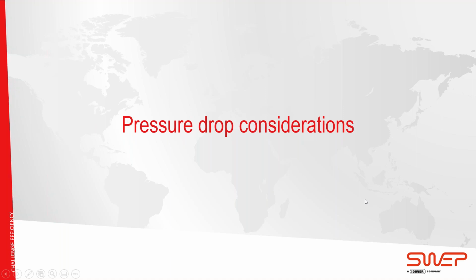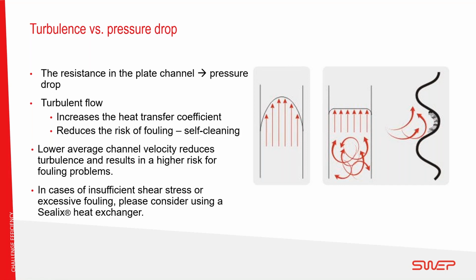So now to move on to some pressure drop considerations that need to be considered in the selection of brazed plates. First of all, we have turbulence against pressure drop. The resistance in the plate channel actually creates turbulence, and this is necessary for high heat transfer coefficients. A resistance to the flow creates pressure drops, and so there's always a trade-off between good heat transfer and pressure drop. For a good design, the fluid velocity must be high enough to give fully developed turbulent flow. When the flow is turbulent, we also see high values for shear stresses, which creates a self-cleaning effect, and that can greatly reduce any fouling and scaling.